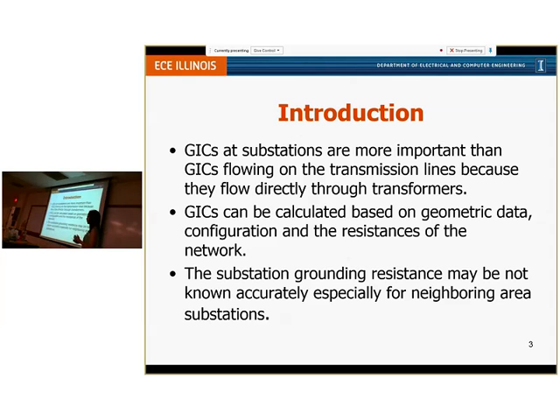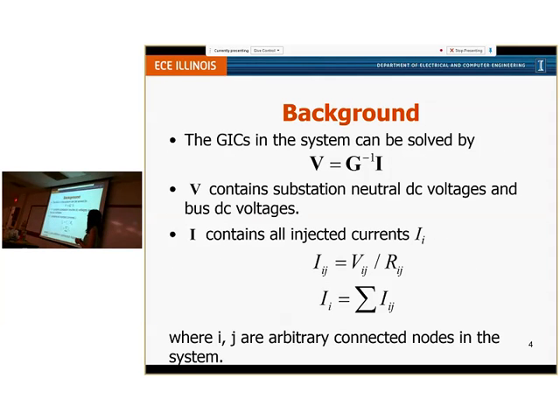Although the resistance values of the transmission lines and the transformers are usually known with high precision, the value of the grounding resistance may not be accurately available. That's why in our paper we want to examine the sensitivity of the GIC to the grounding resistance. The GIC in the system can be calculated using first the equation V equals G to the power minus 1 times I, with V containing the substation neutral DC voltages and bus DC voltages. I is the vector containing the injected currents.